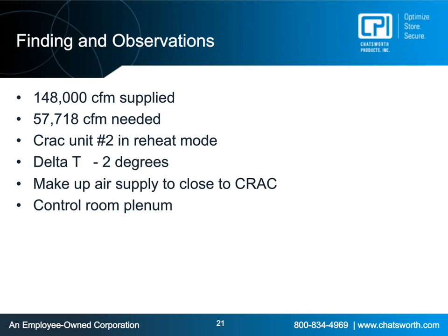Now go back to that California Title 24, and Title 24 said no reheat mode. I didn't mention this before, but the reason we talk about California is California is a huge early adopter. And once California does it, you'll be sure that other states are about to do it. Well, in this scenario, we saw CRAC unit number two was in reheat mode. What had happened is the supply air was going straight down into the return of the CRAC unit. So the supply air was already cold enough. It got into this CRAC unit and said, oh, it's too cold. I need to warm it up by a couple of degrees. So it reheated at 2 degrees and shot it back out.